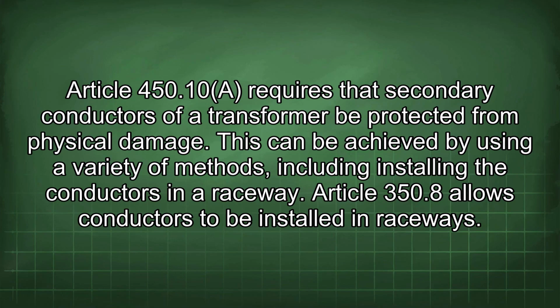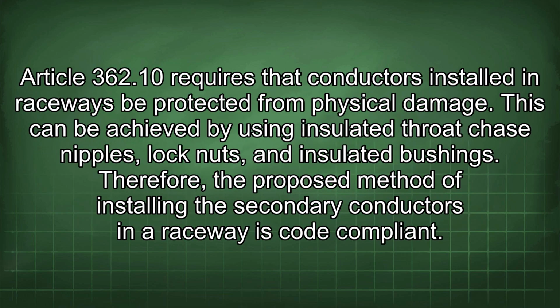Article 450.10 requires that secondary conductors of a transformer be protected from physical damage. This can be achieved by using a variety of methods, including installing the conductors in a raceway. Article 350.8 allows conductors to be installed in raceways. Article 362.10 requires that conductors installed in raceways be protected from physical damage. This can be achieved by using insulated throat chase nipples, lock nuts, and insulated bushings. Therefore, the proposed method of installing the secondary conductors in a raceway is code compliant.